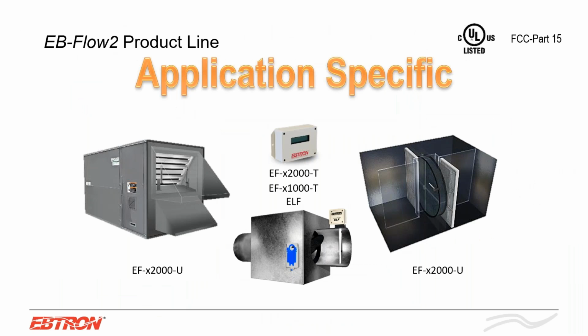All right, let's go into some of the products and we'll open this up to questions. So I was talking about terminal measurement, for DOAS units coming into, for terminal measurement going into individual spaces and zones. Well, this product is something that you would use there, right? So we have the EF2000T, which is designed really for round ducts, 4 to 16-inch round ducts, plus or minus 3% accuracy. And with all of our products, again, you have flow and you have temperature. And with our gold series, you have that humidity or dew point or enthalpy measurement. So you're always getting 2 points of measurement.